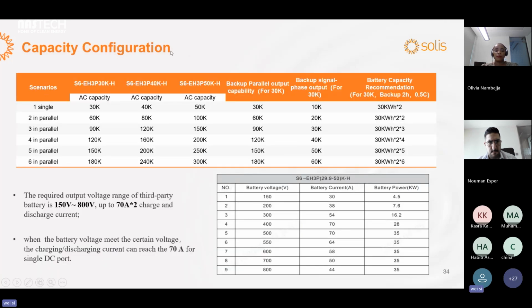Okay, it is about the capacity configuration. For different regions or different customers, one problem is that they often ask me about the charging current. For example, if the voltage of the battery is very low, some customers use a battery with 200 volts or 300 volts, so they can't get the maximum current up to 140 amperes, like we said.